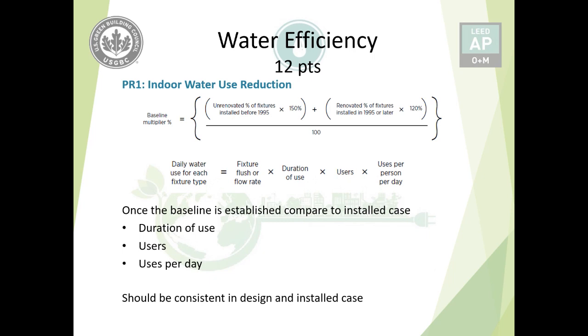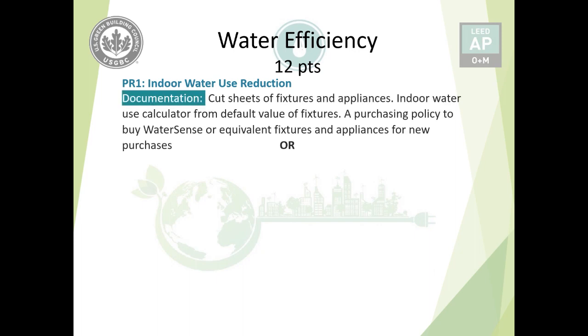The formulas allow you to take out the baseline multiplier percentage based on the certificate of occupancy or renovation — 150% or 120%. The daily water use for each fixture type equals fixture flush or flow rate times duration of use, times uses per person per day. Once the baseline is established, compare it to the installed case inside the building. The number of people in the design case should equal the number of people in the actual installed case. Submit cut sheets or data sheets and subsequent calculations. There should be a policy to buy WaterSense or equivalent fixtures for any new purchases.